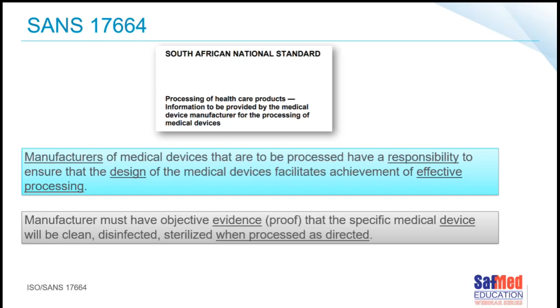Now, some of you may be aware of some of the outbreaks that were related to flexible endoscopes, and in some of those incidences, in some of those court cases, what had happened was that even after following the instructions for use, the staff were still not able to decontaminate the devices correctly. So, very, very important to follow the manufacturer's instructions for use. Let's have a look at an example of one of these instructions for use.